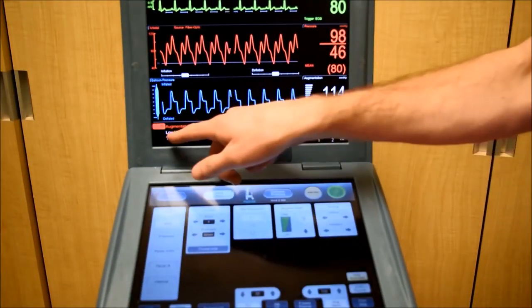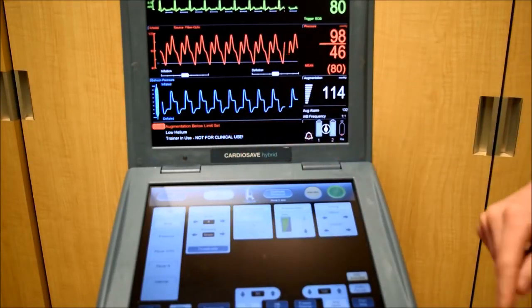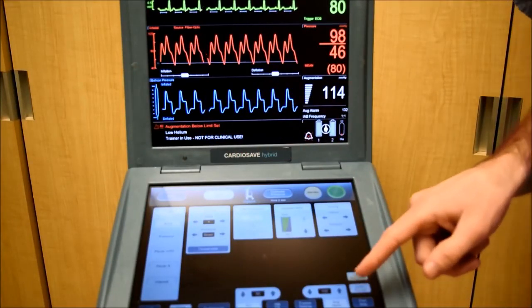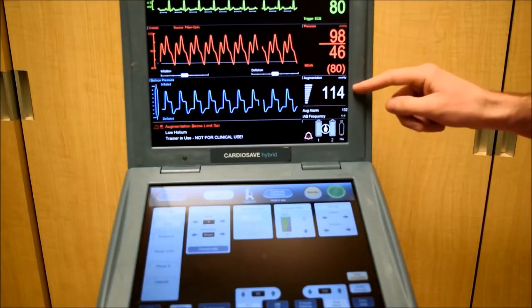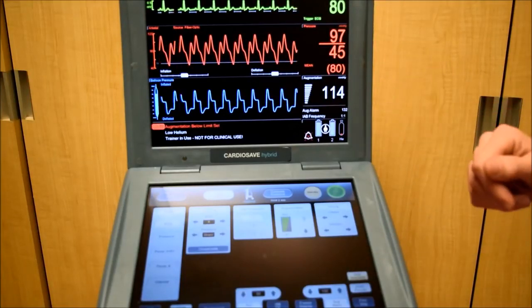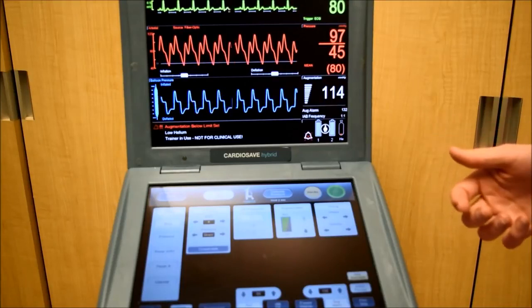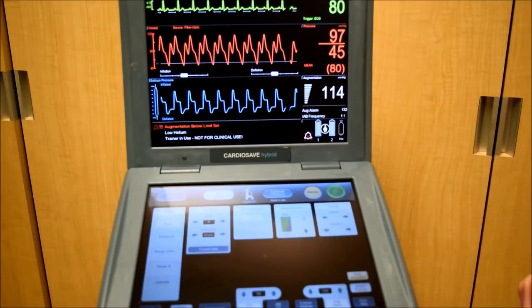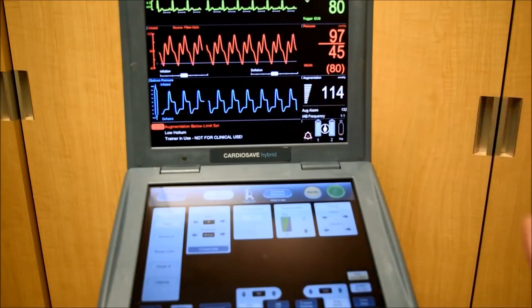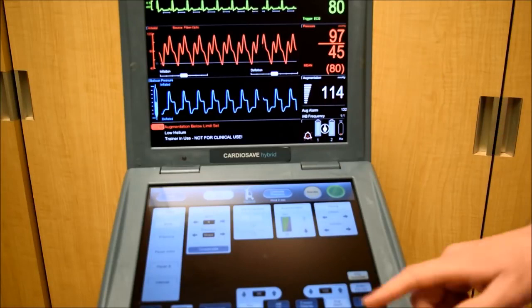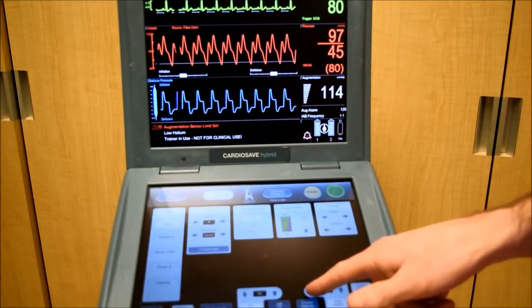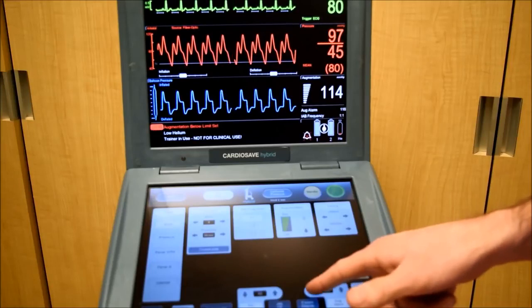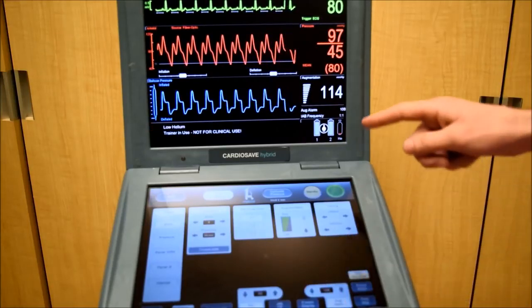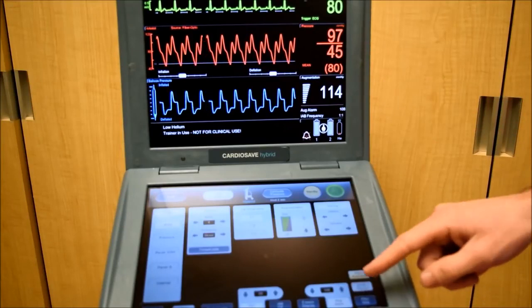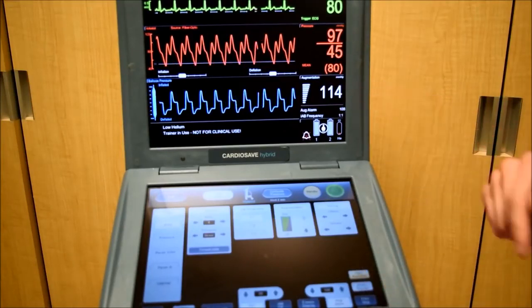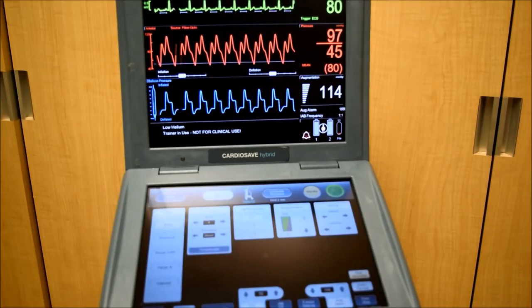If you get the alarm augmentation below limit set, that means the augmentation alarm you have set is greater than the augmentation pressure here. This augmentation pressure is the pressure that the balloon is filled to. To adjust the augmentation alarm and get rid of the alarm here, lower your augmentation alarm set limit. Once we're below 114, or our augmentation pressure, the alarm disappears.